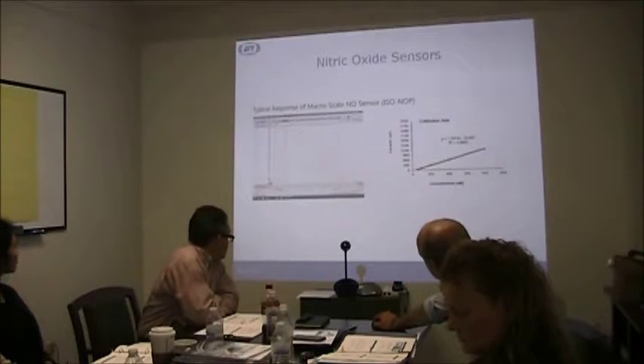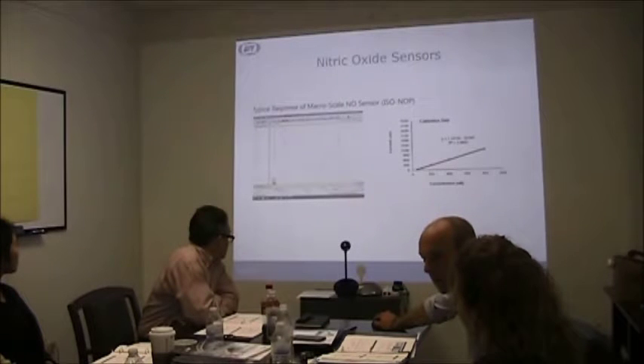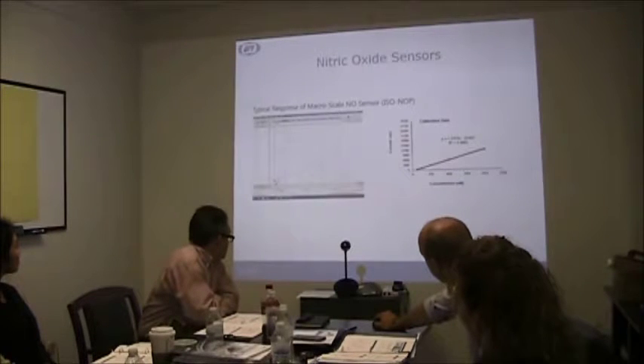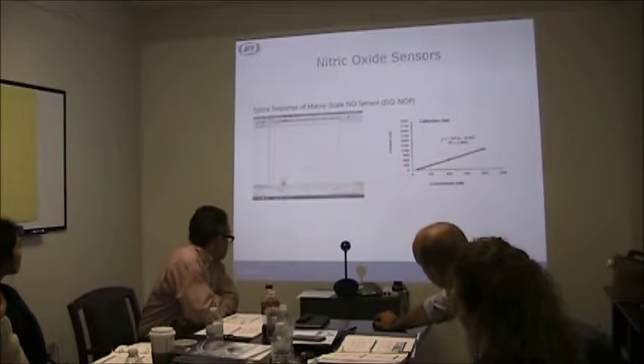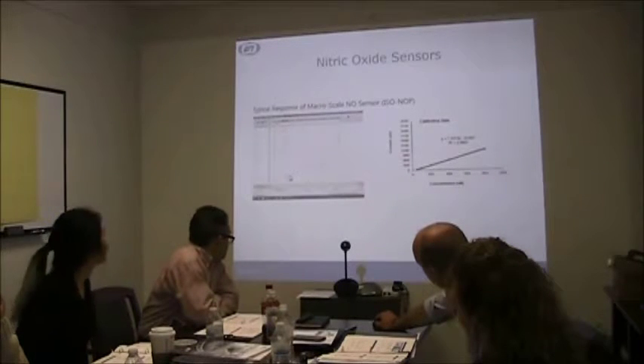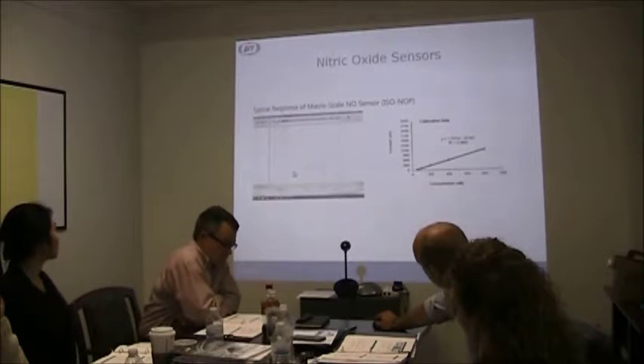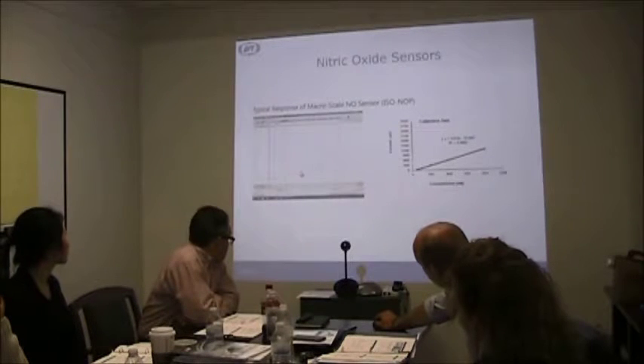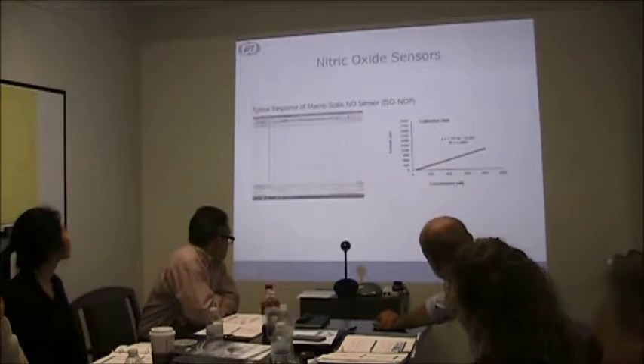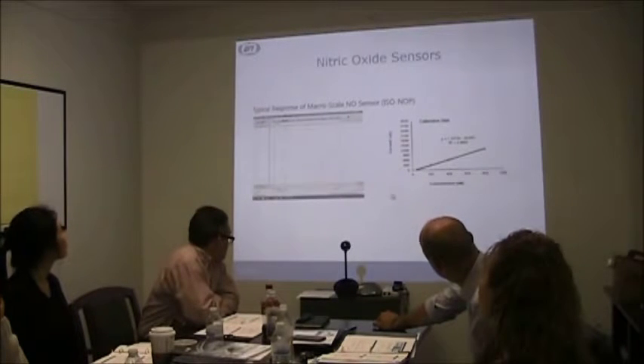What is happening on the curve here is, at this point where you see this slope before it starts to plateau, this is the part where the sensor is detecting the nitric oxide and generating a response, which is this plateau of the curve. Then this is the part where it starts to reach its maximum potential, and then the nitric oxide starts to decay rapidly, which we are able to catch. Then the same thing with the next plot. If you double the concentration, the curve doubles in height, hence the linearity of the sensor. We go through with 5 different points here, and as you can see, the linearity is very well over 99%.